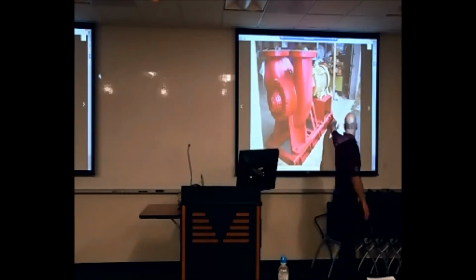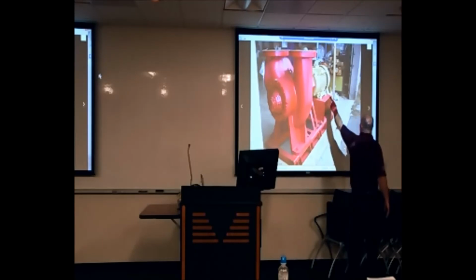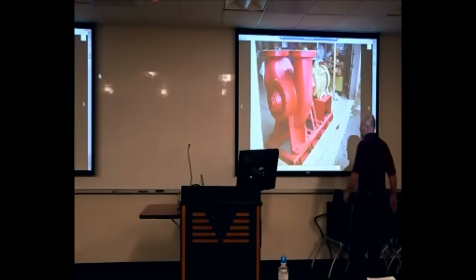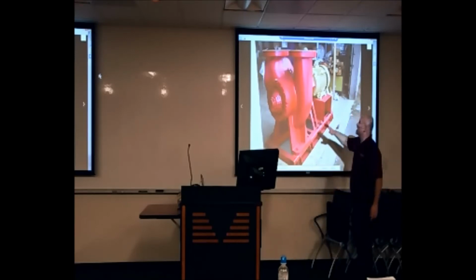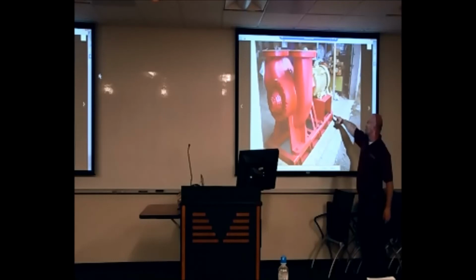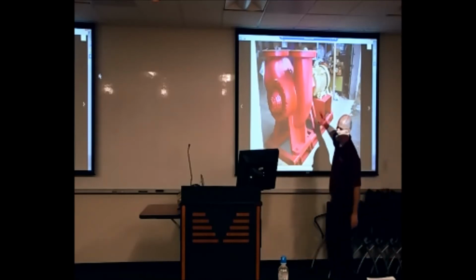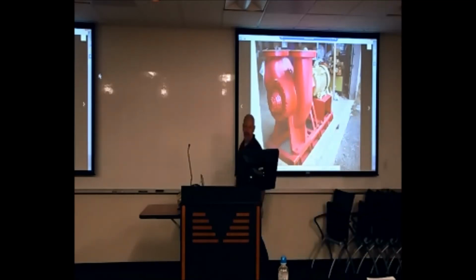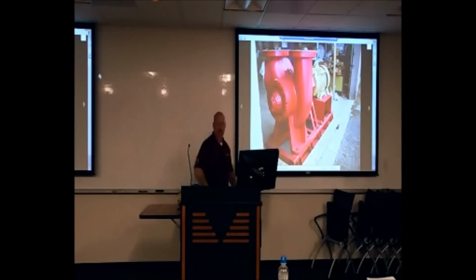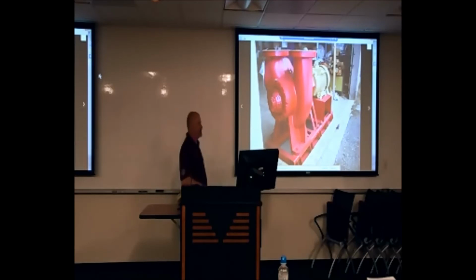is you notice these slots on the bottom of the saddle and the base here. If you want more room between the pump and motor, loosen these bolts down here as opposed to removing the motor, because essentially this just slides forward and back and you don't lose your alignment. So you can actually slide the motor back. In this case, it looks like it's pretty much all the way back, but I think on yours out there, you'll find there's about another 6 to 10 inches of slide space, and you can slide the motor away from the pump end, and it just gives you a little bit more room to get in front of the thing without the shaft poking you in the back.